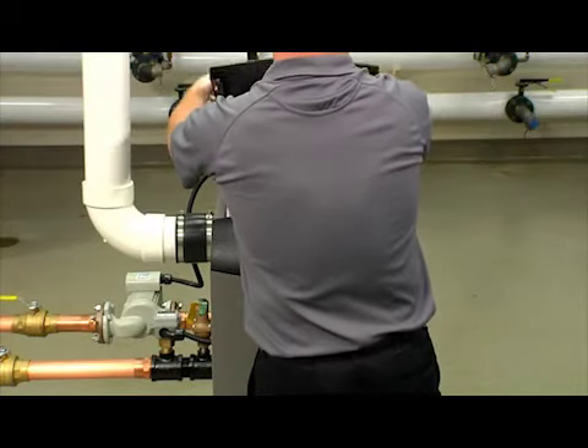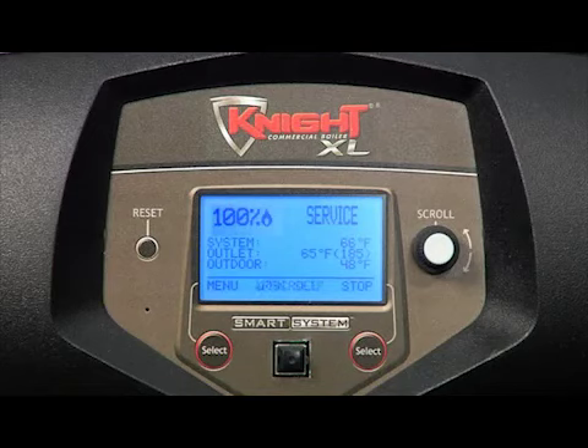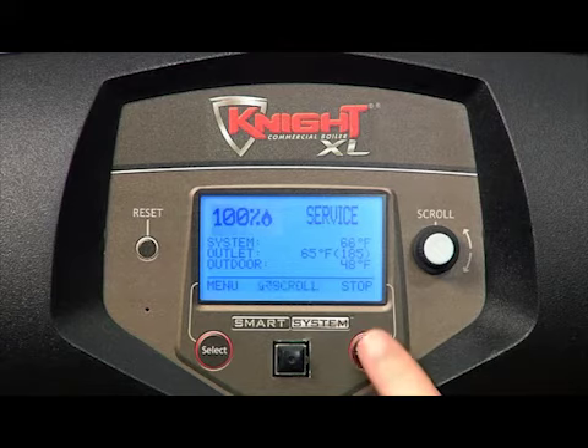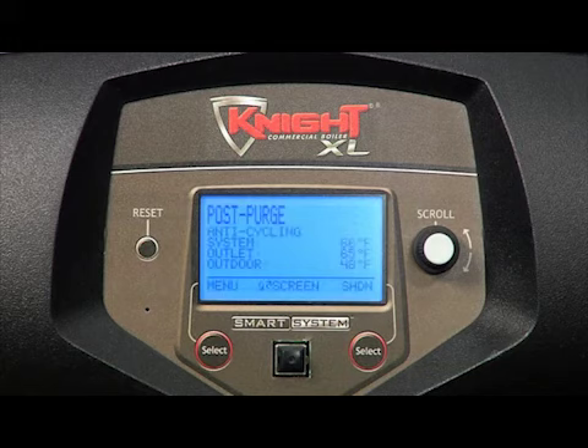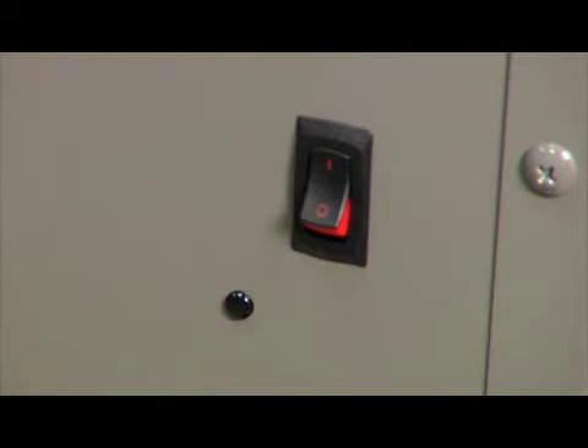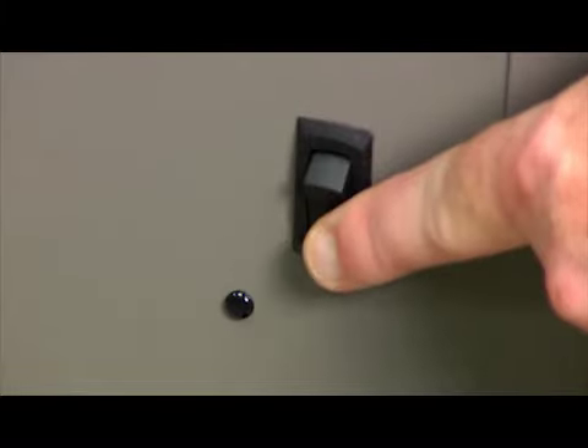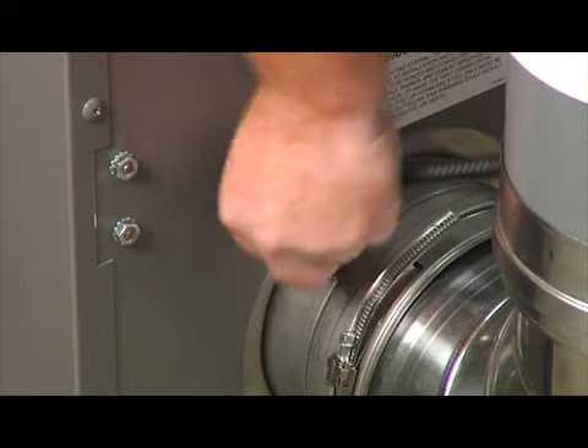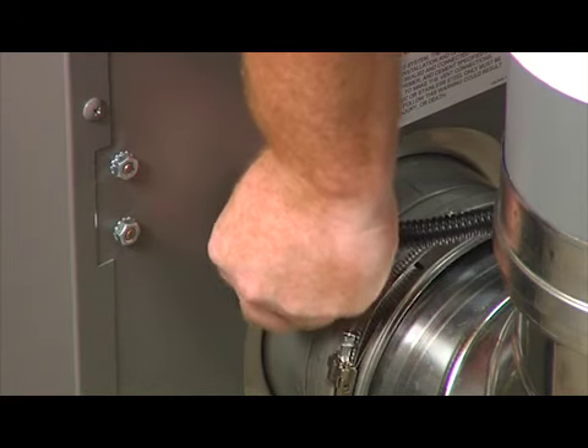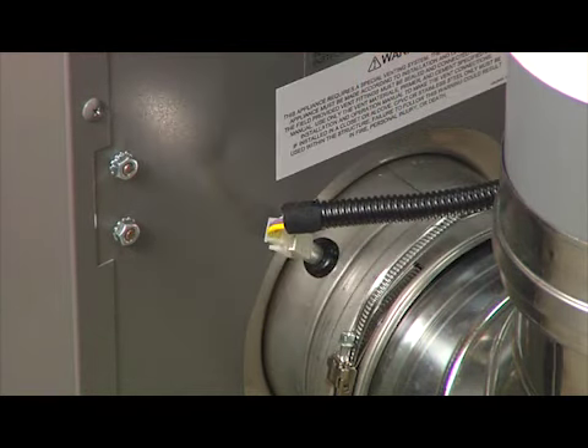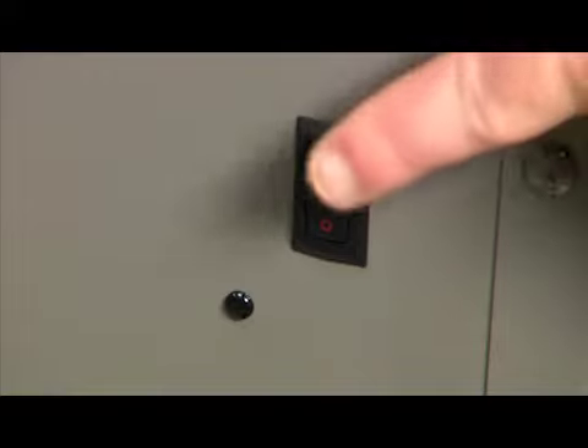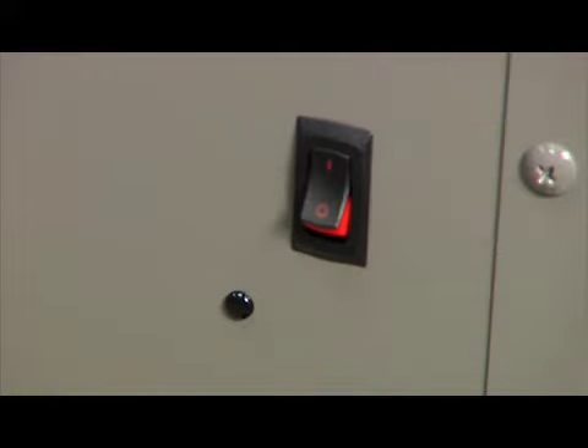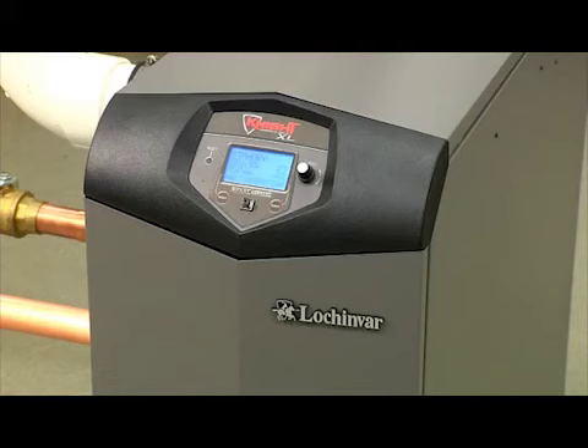Replace the top panel on the unit. Once the combustion analysis is complete, press the right select key to take the unit out of service mode. The unit will return to normal operation. Turn the on-off switch to the off position. Replace the rubber grommet and flue sensor in the vent connection. Turn the on-off switch to the on position. The unit is now ready to accept a heat demand.